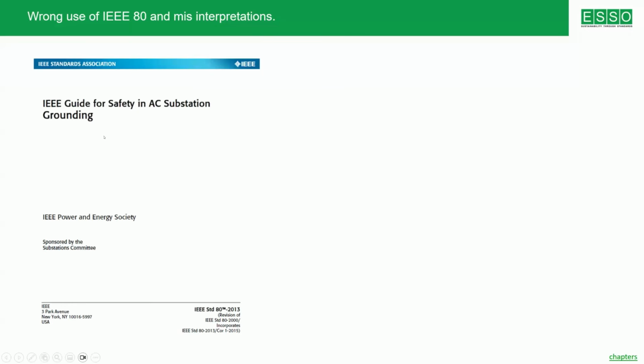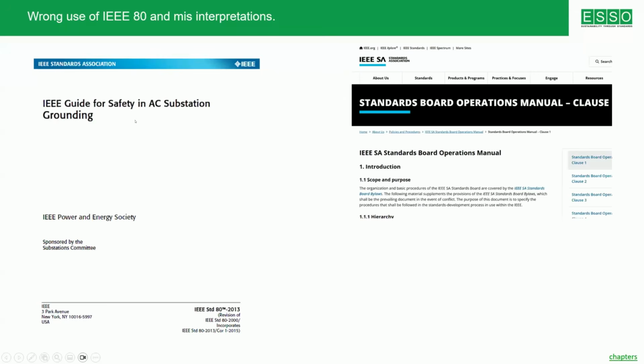In some of the projects, one of the trends which we always see, especially in large projects, is that the electrical engineer wants to make a calculation of an earthing. And then the calculation is as per IEEE 80. Please note, IEEE 80 is an IEEE guide for safety in AC substation grounding. If you look at the website of IEEE, of course, IEEE standards are extremely good, very, very good standards. But the problem is we are applying it in a wrong way.